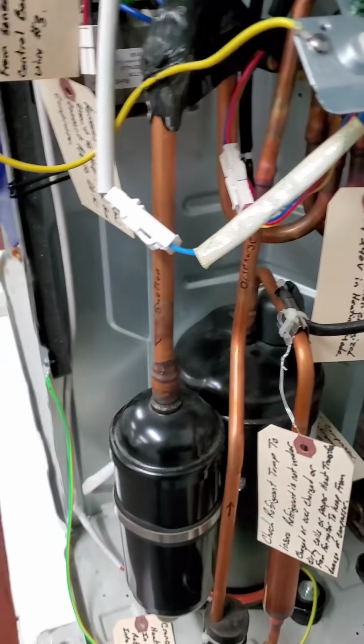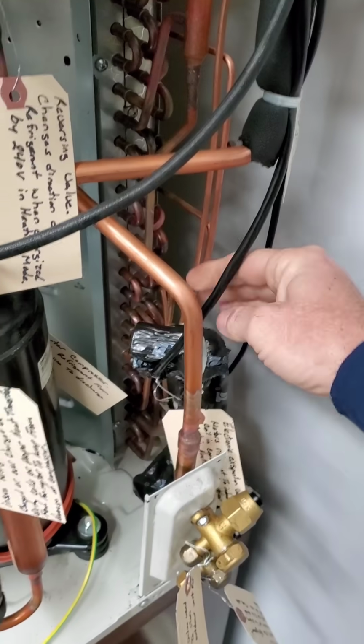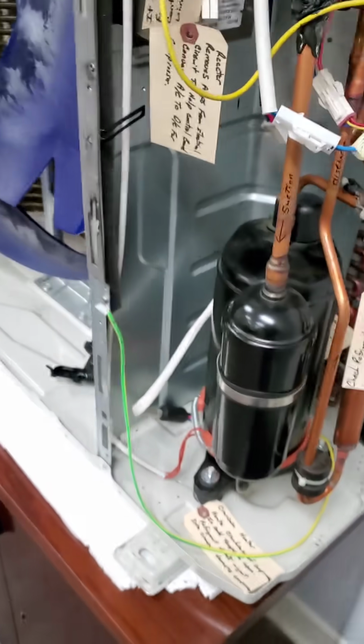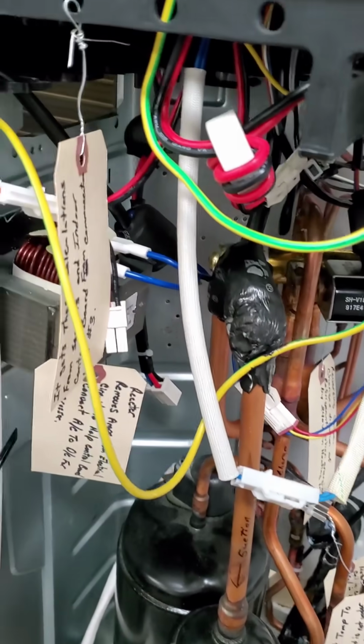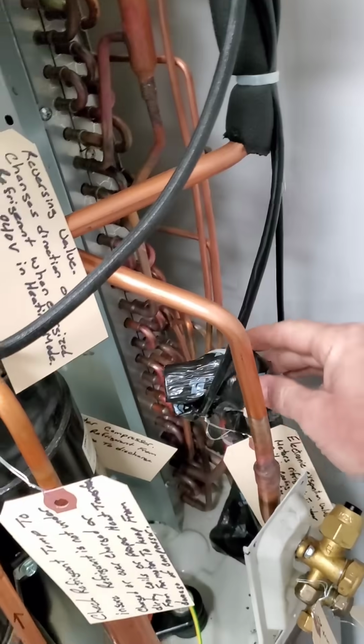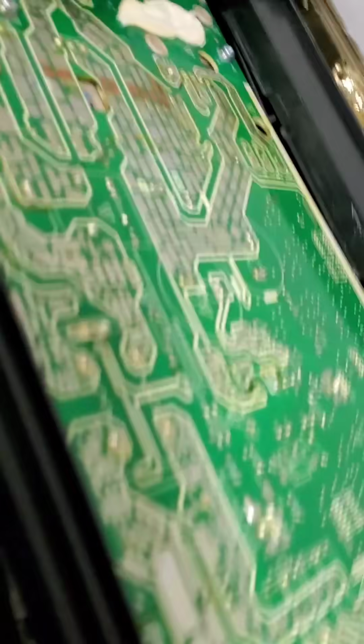So you can unplug that. Normally, they will not ever throw a code for an EXV valve. Unplug the EXV, see if it goes away. It's an easy way of troubleshooting. If it does go away and the system operates, then you need to replace the EXV. And normally you don't have to replace the whole one, just the head. The head comes off. And the 5 volts I was talking about, let me find it on the board here.